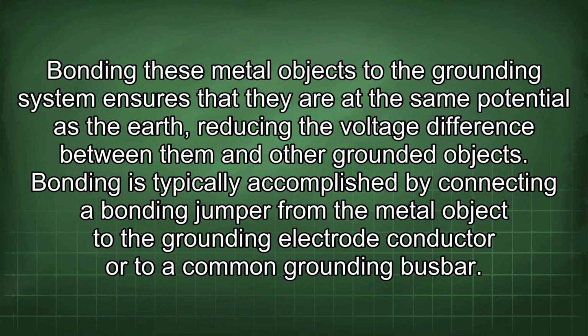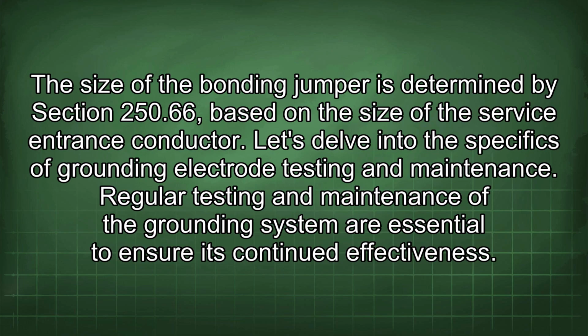Bonding is typically accomplished by connecting a bonding jumper from the metal object to the grounding electrode conductor or to a common grounding busbar. The size of the bonding jumper is determined by section 250.66 based on the size of the service entrance conductor.